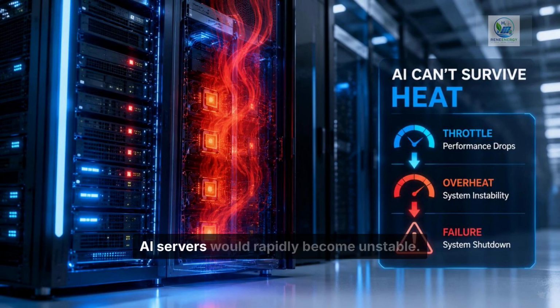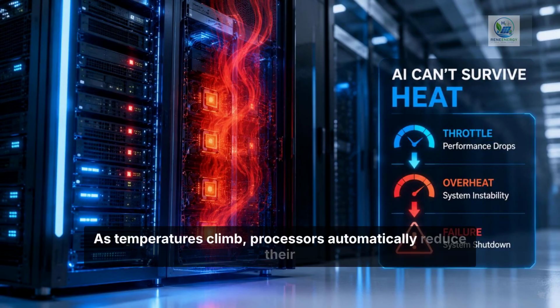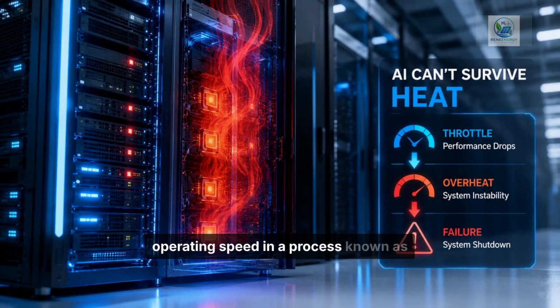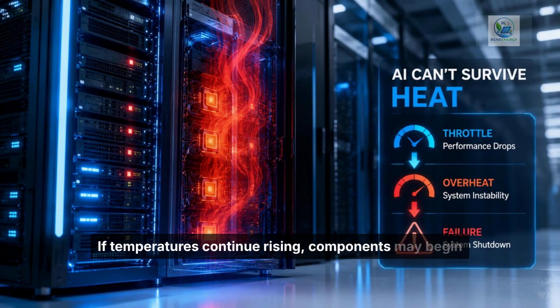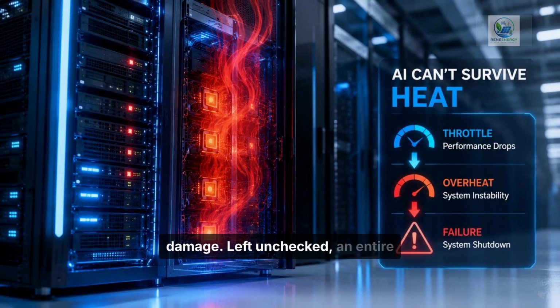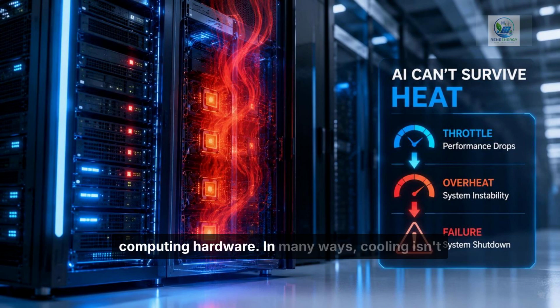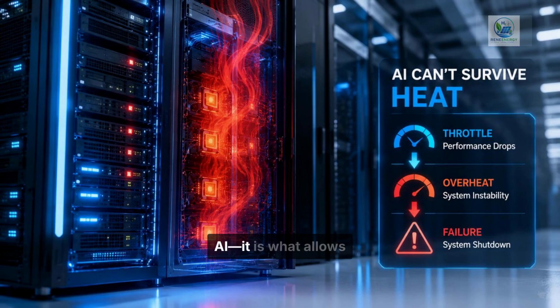Without cooling, AI servers would rapidly become unstable. As temperatures climb, processors automatically reduce their operating speed in a process known as thermal throttling. If temperatures continue rising, components may begin shutting down to protect themselves from permanent damage. Left unchecked, an entire AI cluster could go offline. That's why every modern AI data center invests as much engineering into cooling infrastructure as it does into computing hardware. In many ways, cooling isn't simply supporting AI, it is what allows AI to exist in the first place.